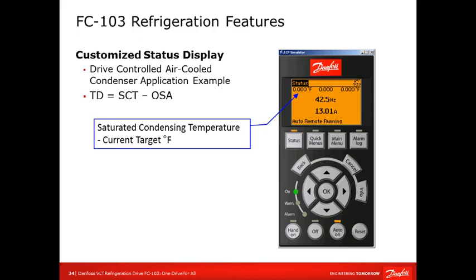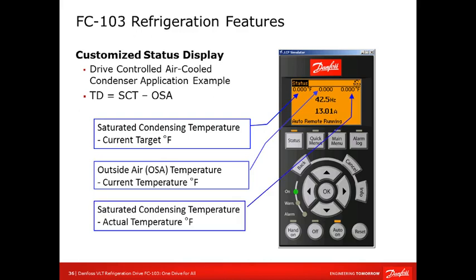What we can do too with the drive is a very user friendly customized display. The operator or the OEM can decide what they want to see on the screen of the LCP. LCP is like an HMI, Danfoss lingo, local control panel. So we can utilize the display to show what you want to see. In this case, it's just an example: for the condensing application, you can set it to see the condensing temperature, outside air, and saturated condensing temperature. It's flexible, and we're just trying to show you that you can utilize it for your specific application.